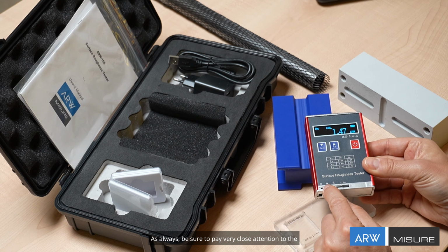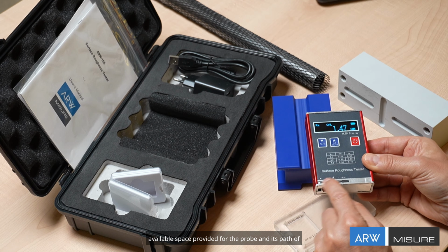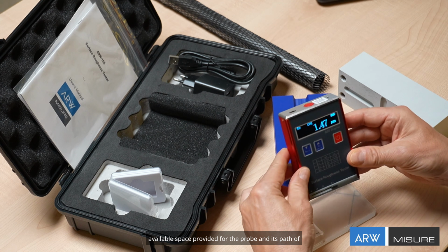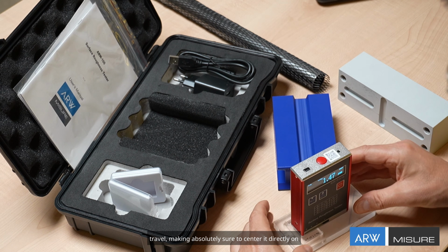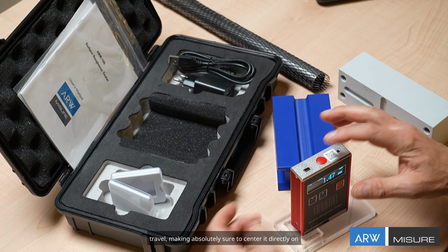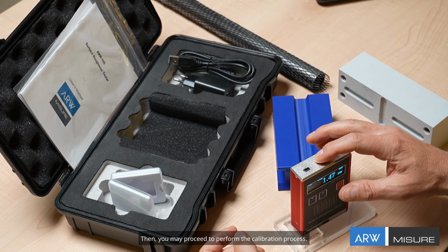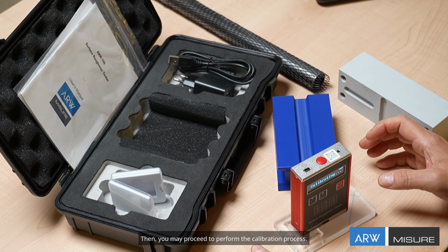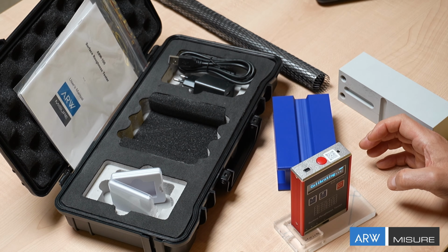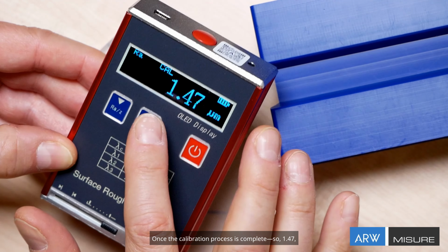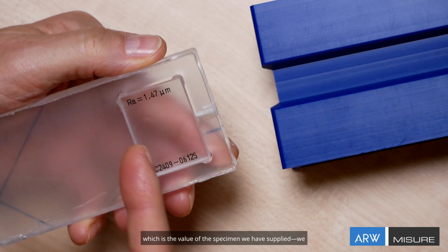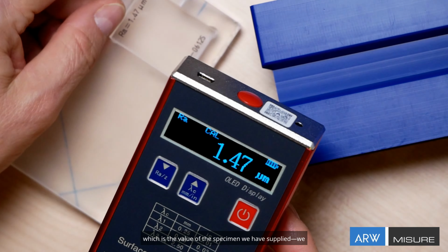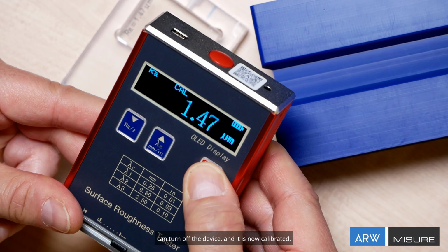As always, be sure to pay very close attention to the available space provided for the probe and its path of travel, making absolutely sure to center it directly on the specimen. Then you may proceed to perform the calibration process. Once the calibration process is complete, so 1.47, which is the value of the specimen we have supplied, we can turn off the device and it is now calibrated.